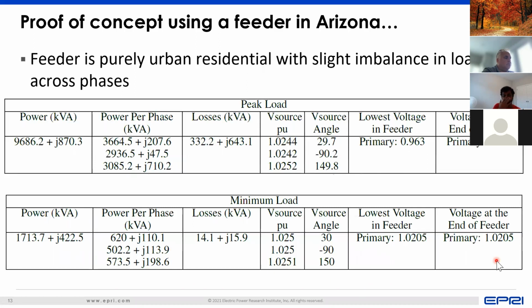An example or proof of concept of this was a feeder that we took up from Arizona, where the feeder is purely urban residential. So pretty much rooftop PV is the DER in that feeder. There is a large variation between the peak load and the minimum load, pretty much 8 megawatt or 7 megawatt of variation in the peak load versus the minimum load. And then there is not much imbalance. There's only a slight imbalance across the various phases.